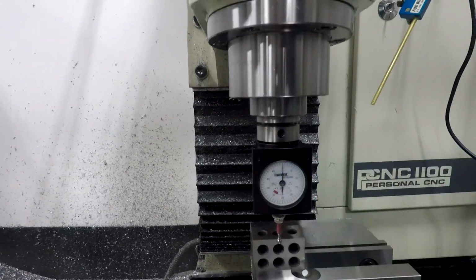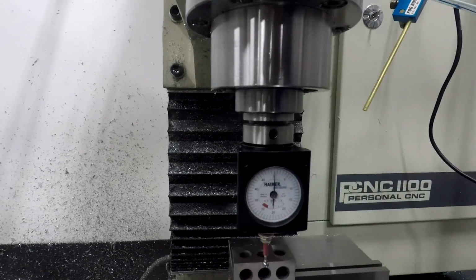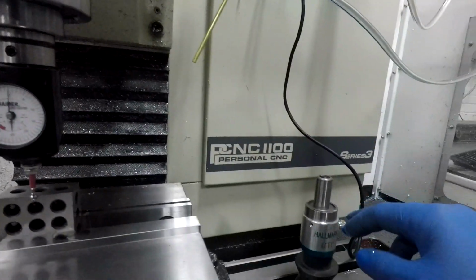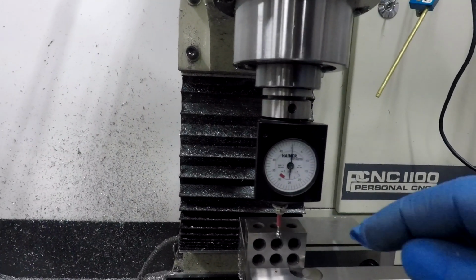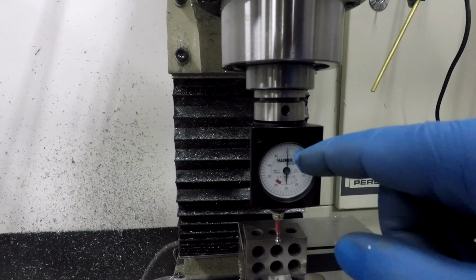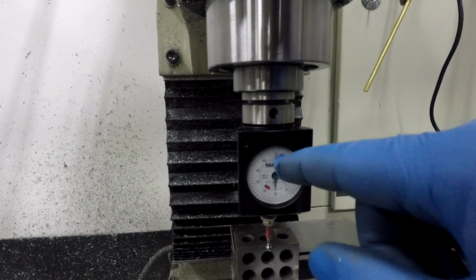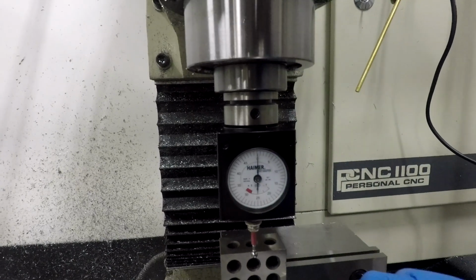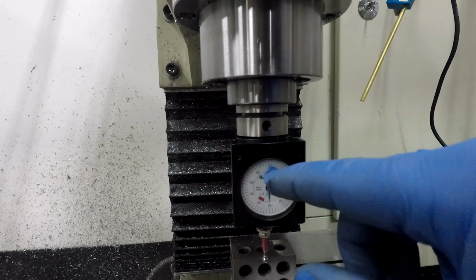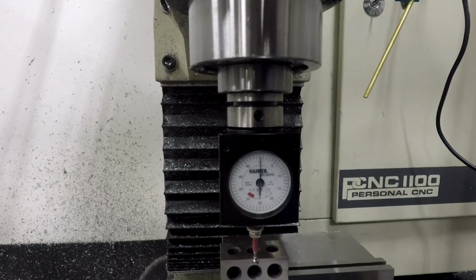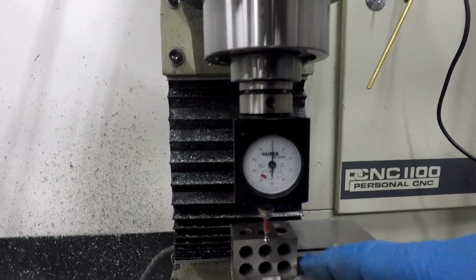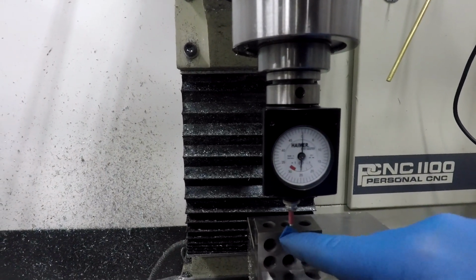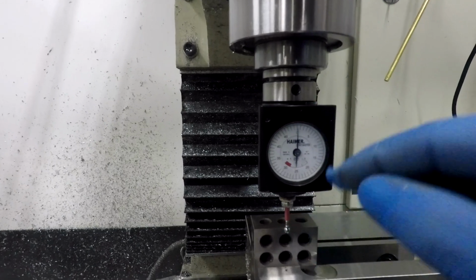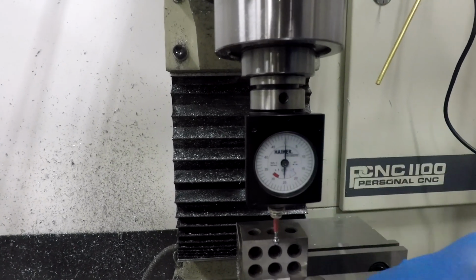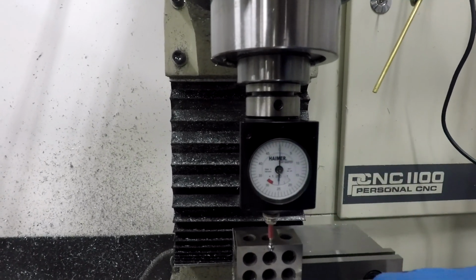And this is all subjective on how well you check your backlash, because this will automatically factor into backlash because it goes in and comes back out and it sets it again. This is also depicted on how well you see your up and down arrow or your needle on the 0. Also, when you calibrate this needle here, you got to dial it in and make sure it's centered. And so that's also a factor on the 0.